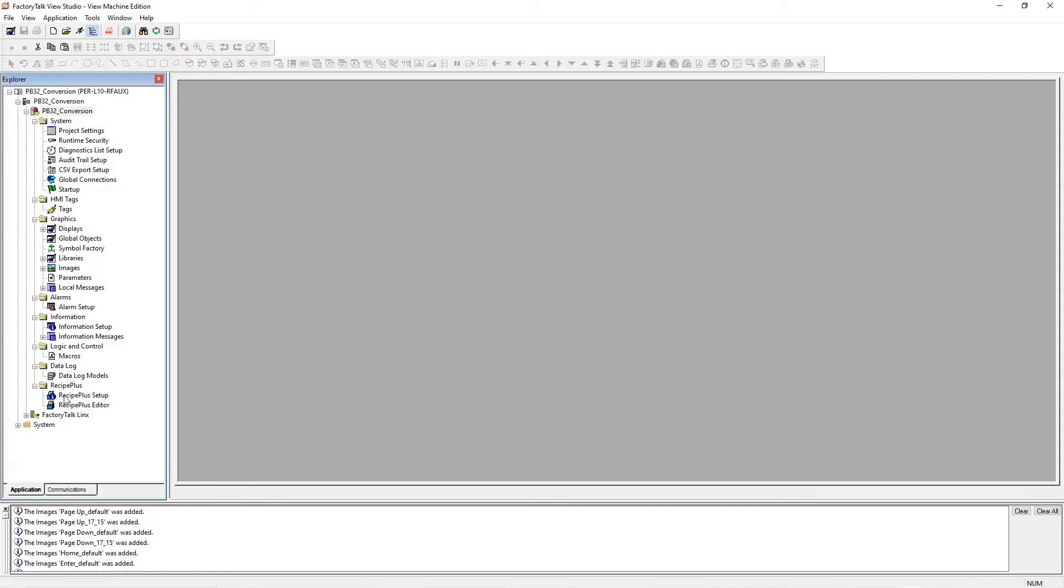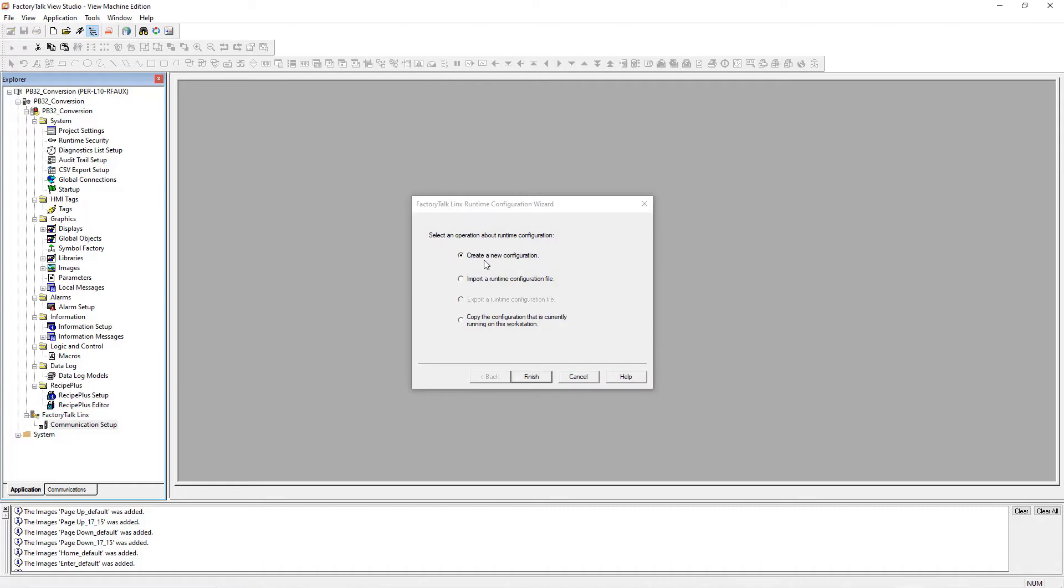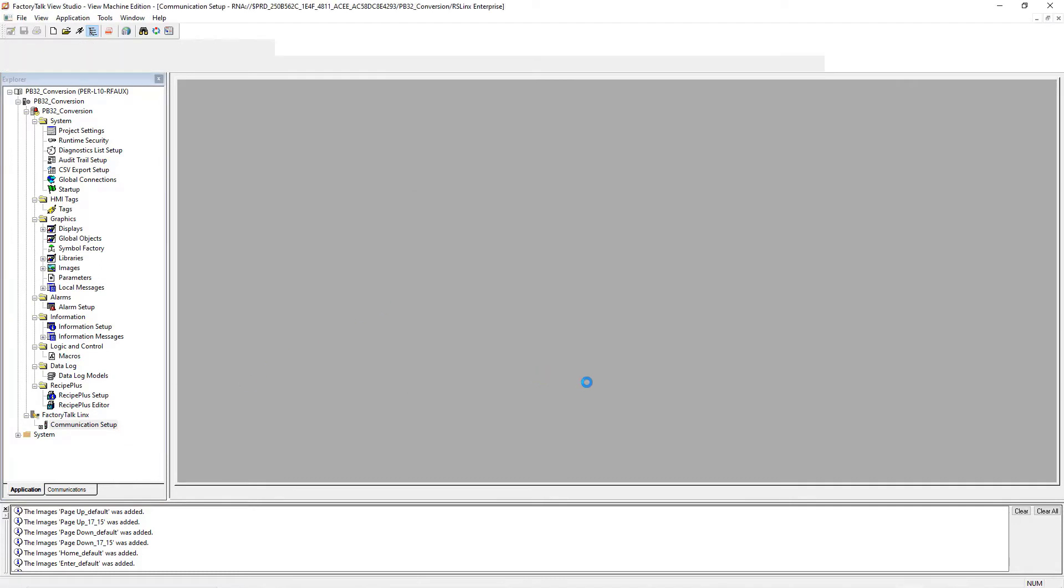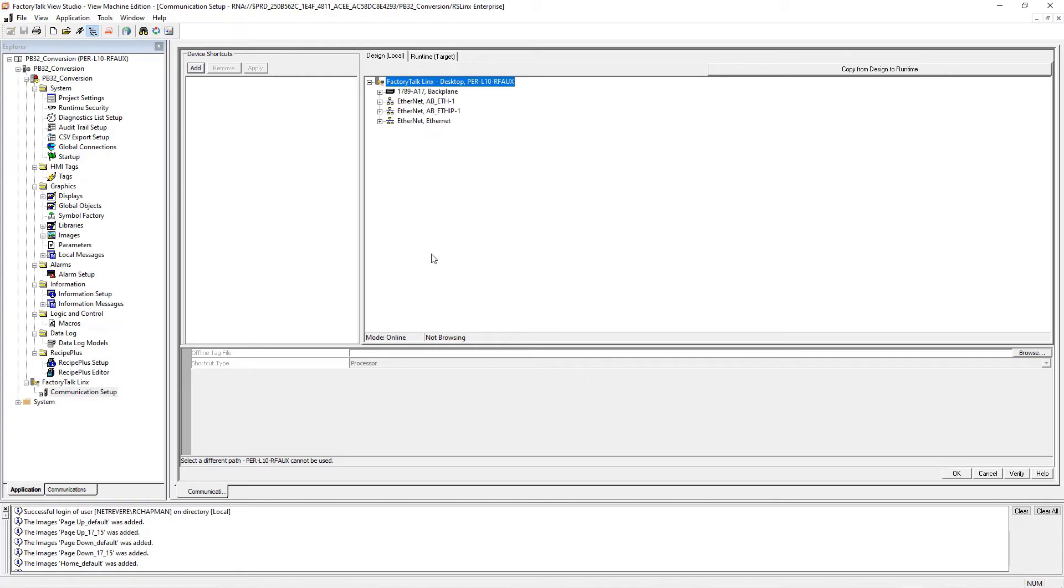We got it converted. So now you want to go into the communication setup and we want to set up the PLC shortcut, which is the path. Create a new configuration here. This is the path that tells the PanelView how to talk to the PLC, where to talk to the PLC. So we're going to add a shortcut here, but we need to make sure this name matches what's in the tags.